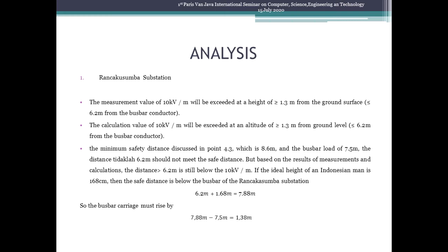If the ideal height of an Indonesian man is 168 centimeter, the safe distance of the Busbar of the Ranca Kusumba substation is 7.88 meter. So, the Busbar carrier must rise 1.38 meter.